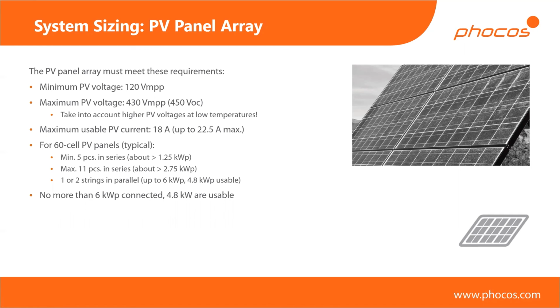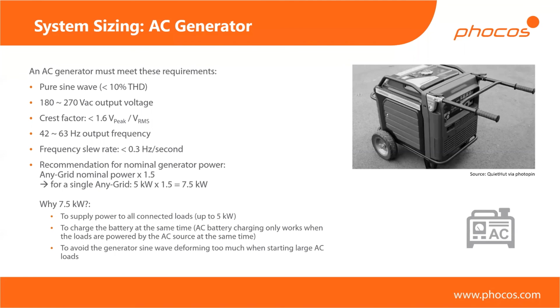And there's a limit to what you can test. So we've tested it up to 6 kilowatt peak, and we know that works. And up to 4.8 kilowatts are truly usable by the inverter when the battery voltage is high and when you have the maximum solar irradiation. For the AC generator, things get a little bit cryptic, so I'll save that as just a pure dictionary for you if you need to look it up, if you want to choose an AC generator to fit to the AnyGrid. What is important, I think, is to have a certain minimum generator size.